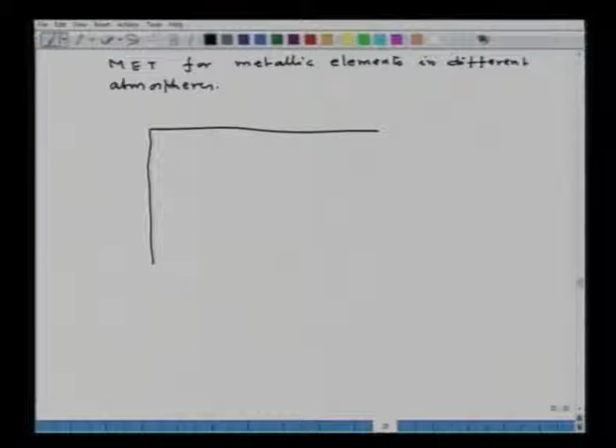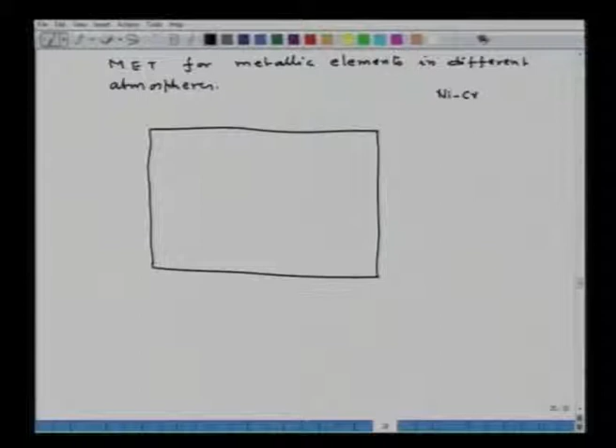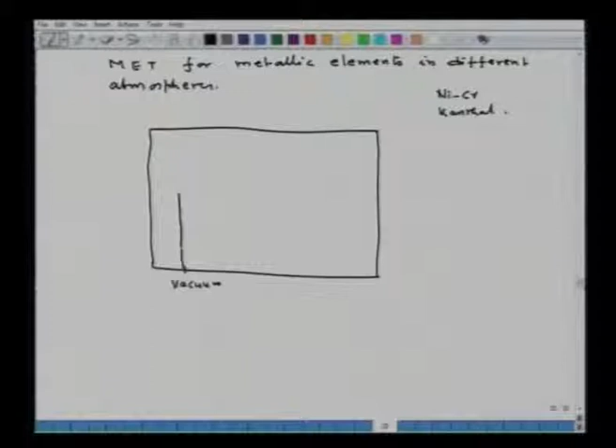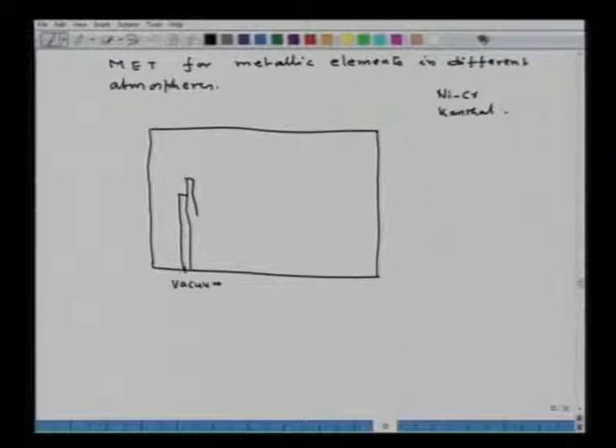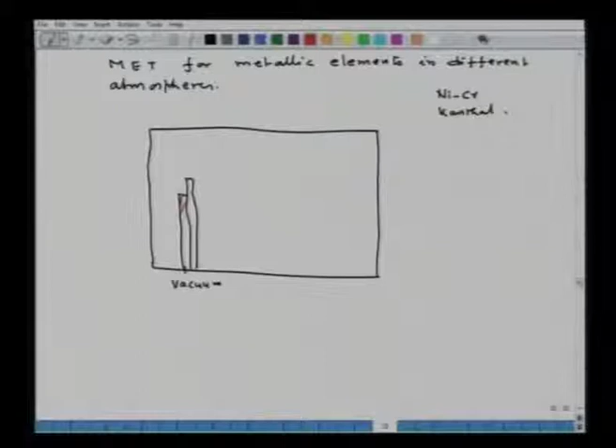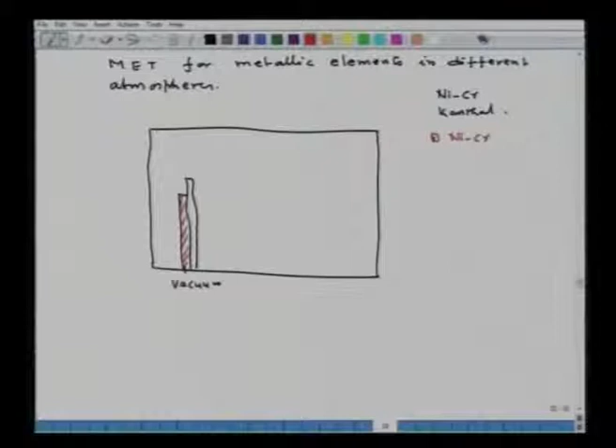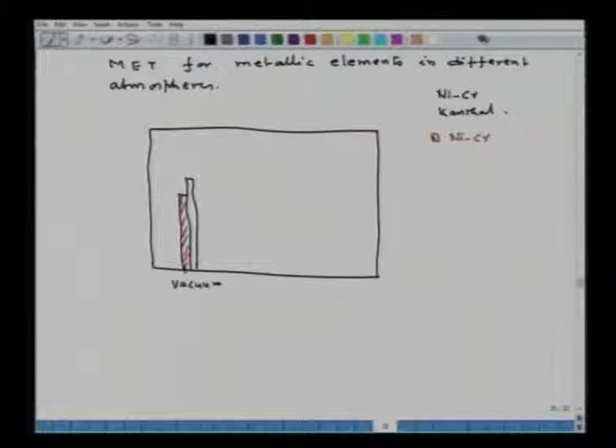Now, their response to the atmosphere will also be different. So, let us consider the maximum element temperature for metallic elements in different atmospheres. Again, I will plot. I have taken two heating elements. One is nickel chromium, that is nichrome, and another is kanthal. So, under vacuum, this one is nickel chromium, whereas this one is the kanthal. So, I am comparing nickel chromium versus kanthal in vacuum atmosphere. Nickel chromium can be used up to 1000 degrees Celsius and kanthal goes up to 1200 degrees Celsius.